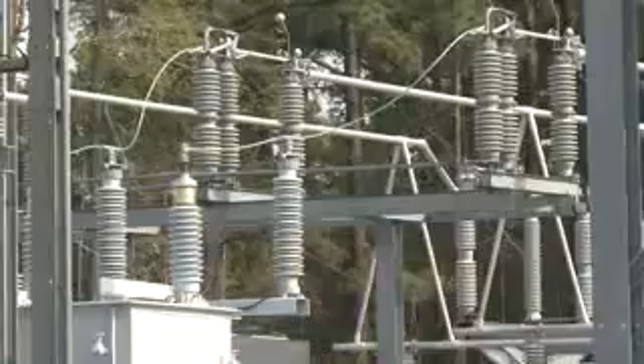Some of the more obvious hazards in substations and switchyards are electrical hazards. Any energized conductor or equipment can be an electrical hazard, such as buses, power transformers, circuit breakers, and other energized conductors and equipment. The hazard is in accidentally contacting an energized circuit. You can't tell just by looking which conductors and equipment are energized and which are not, so the safe approach is to assume they are all energized until you can prove otherwise.